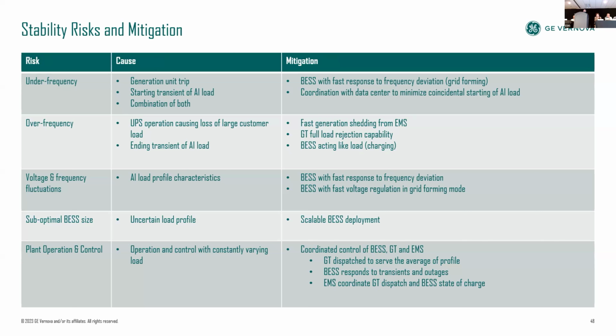We see a frequency event due to either a generation trip or the starting of the AI load, or a combination of those. We have a frequency event due to UPS operations. We can also have voltage and frequency transients when the load profile is running. When it first starts, we have a big transient, but when it's running, the issues still exist. And we need solutions either through BESS or through E-STATCOM type solutions that the previous speaker talked about to mitigate those transients. And there are also issues because the load profiles are changing, as we speak. So there is a risk associated with either overestimating or underestimating the size of the storage that we need. The option is to have a scalable deployment of the resource.